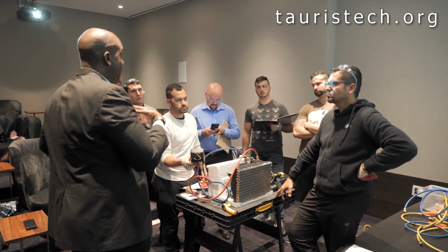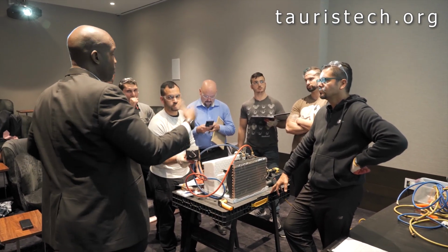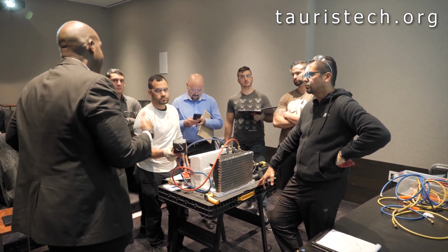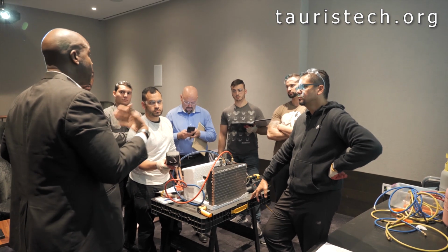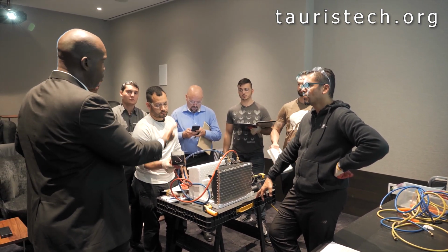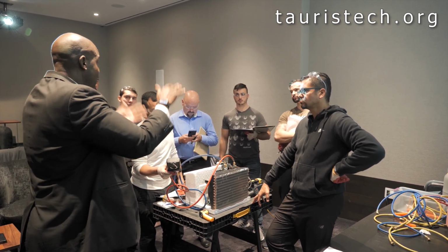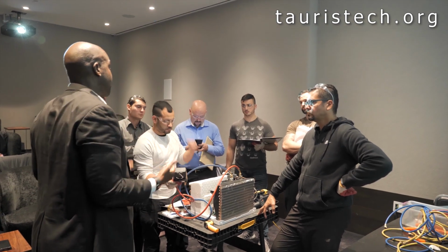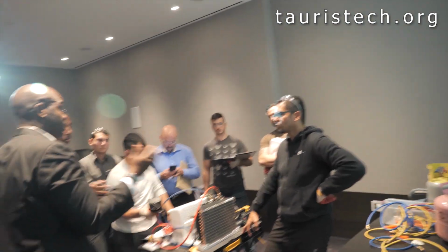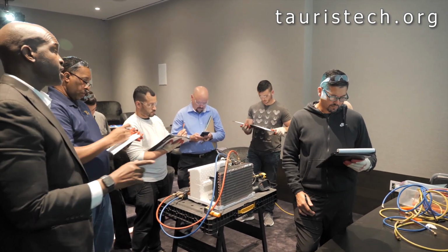degrees. So if I know that I'm supposed to be boiling my refrigerant at 35 degrees, the pressure should be somewhere around 100, and if it's like 80, that means I have a problem. So my machine may be undercharged. Usually on most systems we want to boil at 35 and condense at 105. So if something is off with those numbers, then it's either something wrong with our charge or with some component somewhere in our system. Number 2 is our suction line.